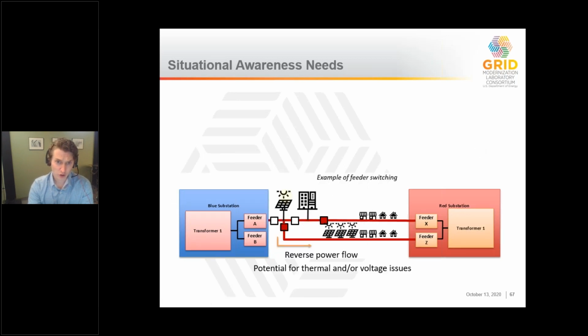the system could be reconfigured. So whereas that large PV unit close to the blue substation may not have had an effect on voltage, just due to where it was located, now that reverse power is going on a different feeder, it could be quite a distance from the substation based on how it's reconfigured.